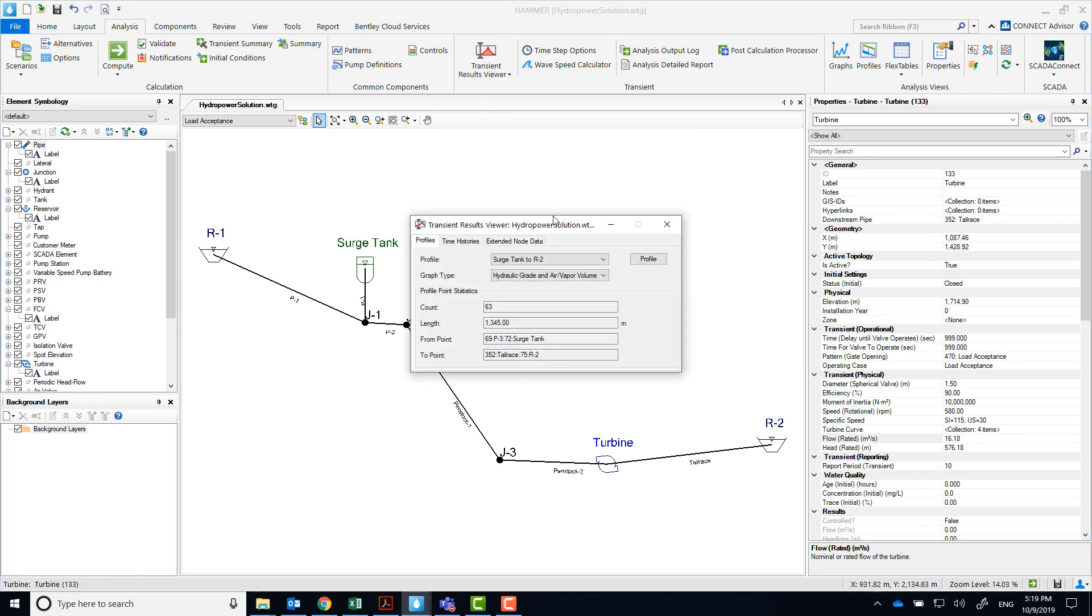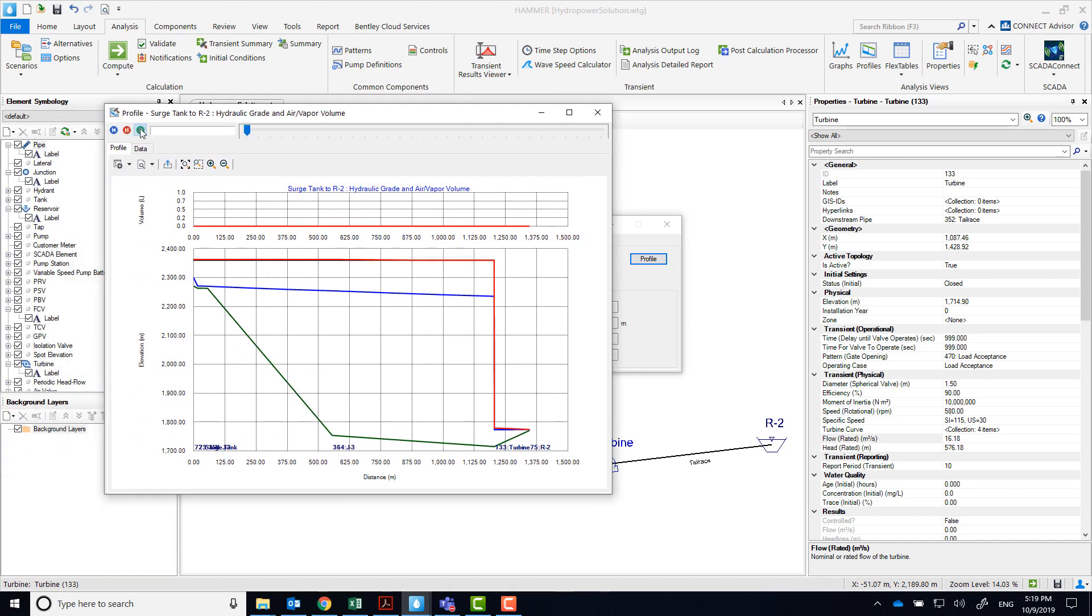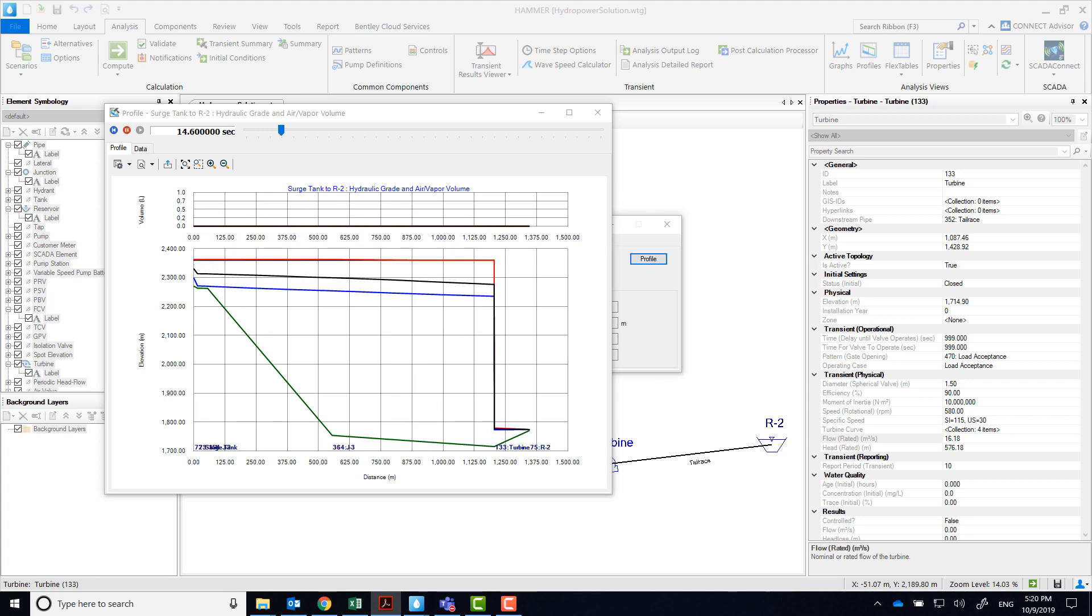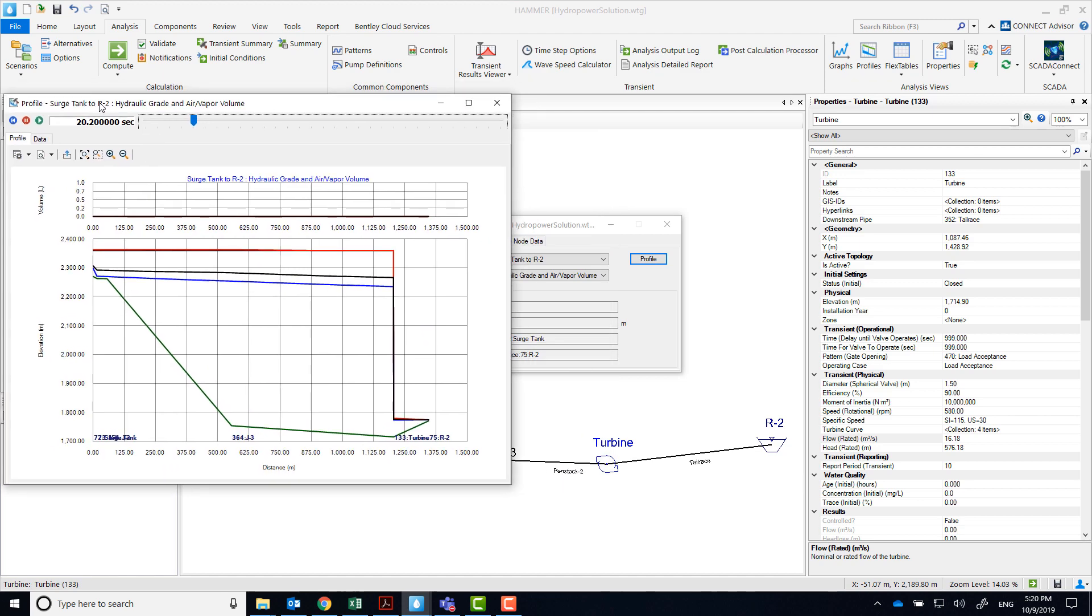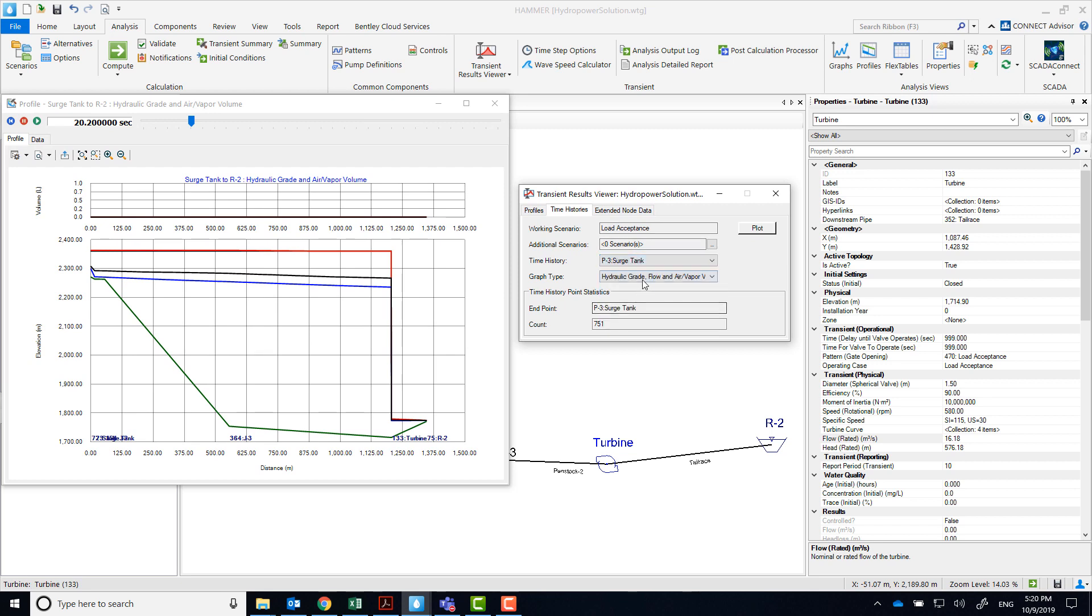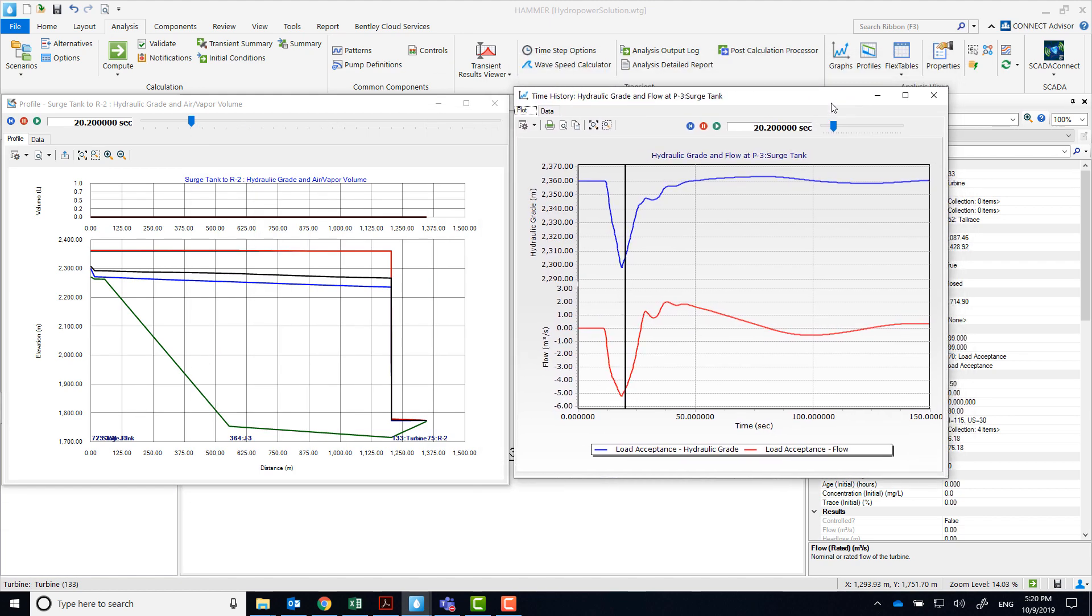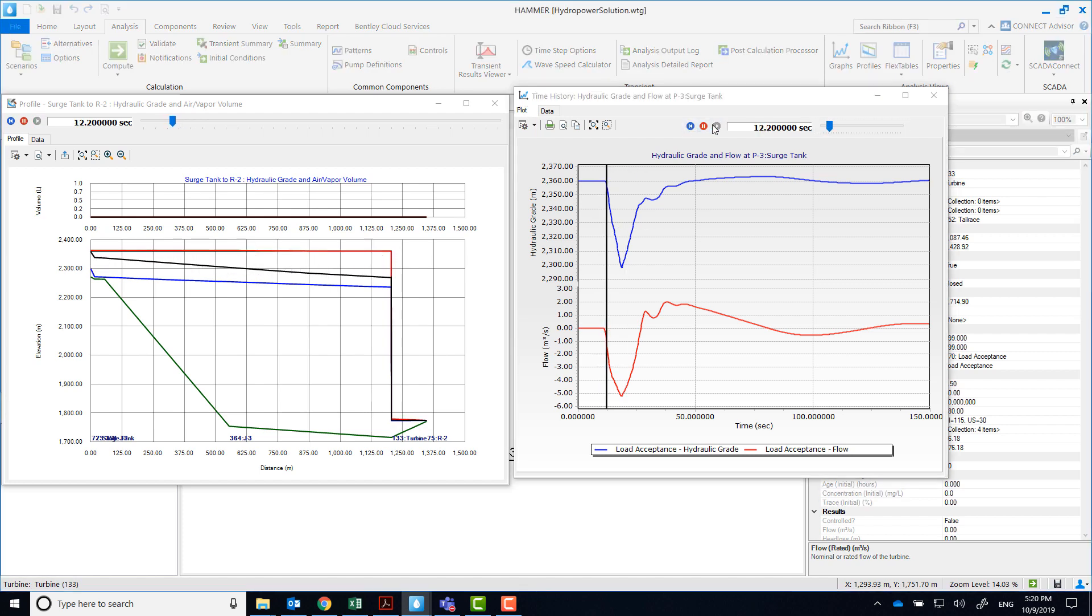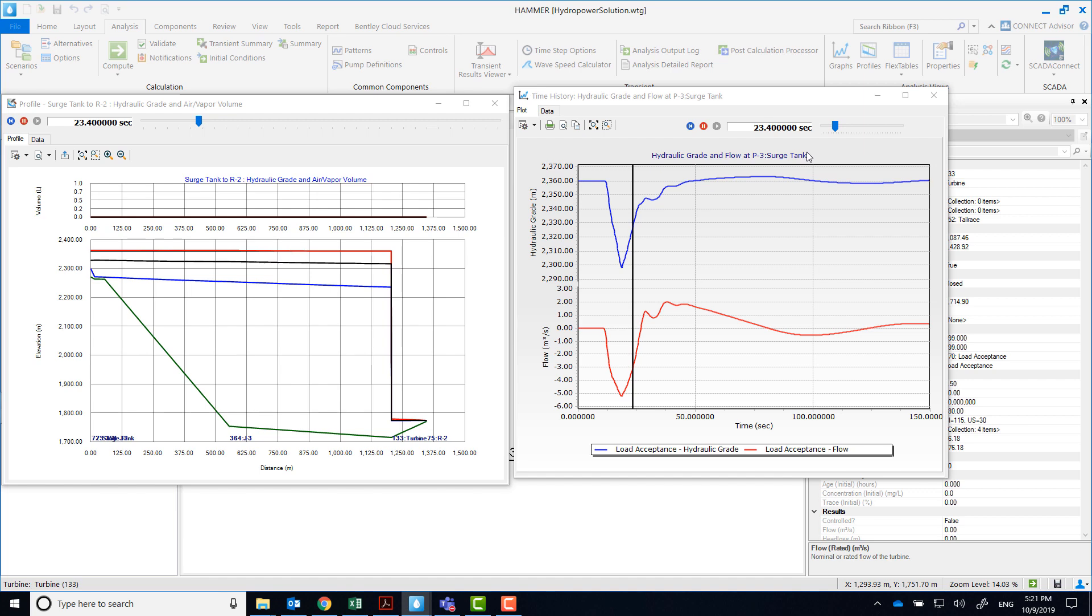Let's take a look at the profile. There are no vapor pockets, and at about 11 seconds, the surge tank begins to drain to compensate for the down surge generated when the turbine starts up, effectively preventing vapor pockets from forming upstream of the turbine. Let's look closely to the surge tank in the time histories. We'll look at flow and hydraulic grade. Here we can see how the surge tank drains right at about 11 seconds, compensating for that drop in hydraulic grade line that was generated when that turbine started up.